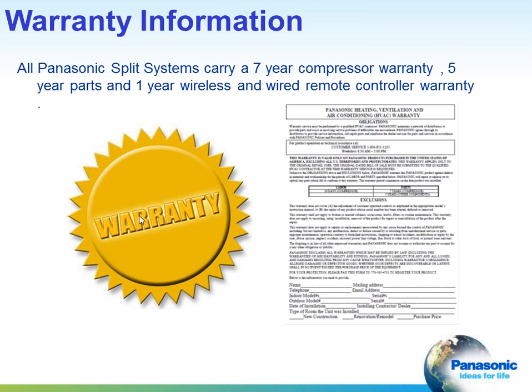Warranty. A 7-year compressor warranty is standard, and if you've gone through the training, there are certain requirements there. We want to make sure that the equipment is installed correctly. Our experience with this equipment is most times when we have a problem, it's an installation issue. So make sure you're comfortable with installing this equipment. If you're not, give us a call and we'll hook you up with some training either online or on a one-to-one basis. 5-year parts warranty and 1-year wireless and wired remote control warranties.